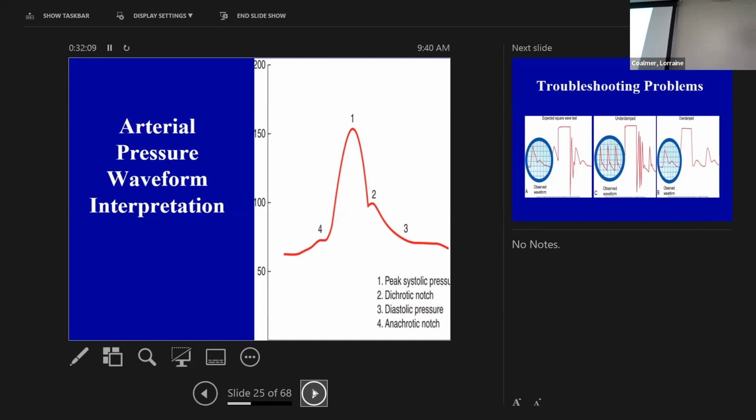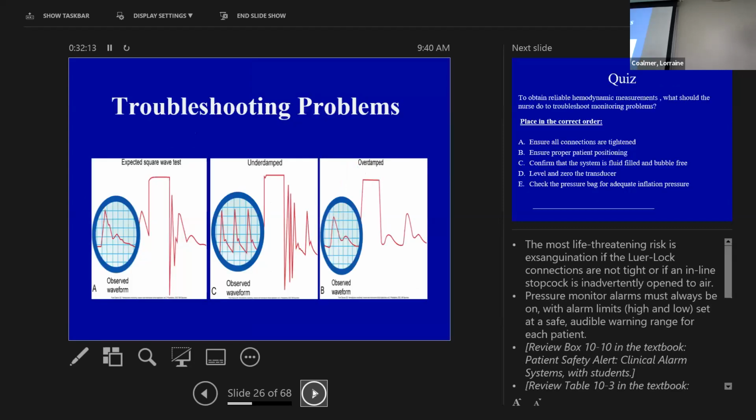Look at that waveform. Make sure that you see a sharp, nice dicrotic notch. Now, couple things. So we saw what the waveform should look like. And one of the things that we could do to make sure that everything's good is we call this the square waveform test. Okay, so do you see the monitor? You see that beautiful dicrotic notch in the very first picture. Sharp, nice.